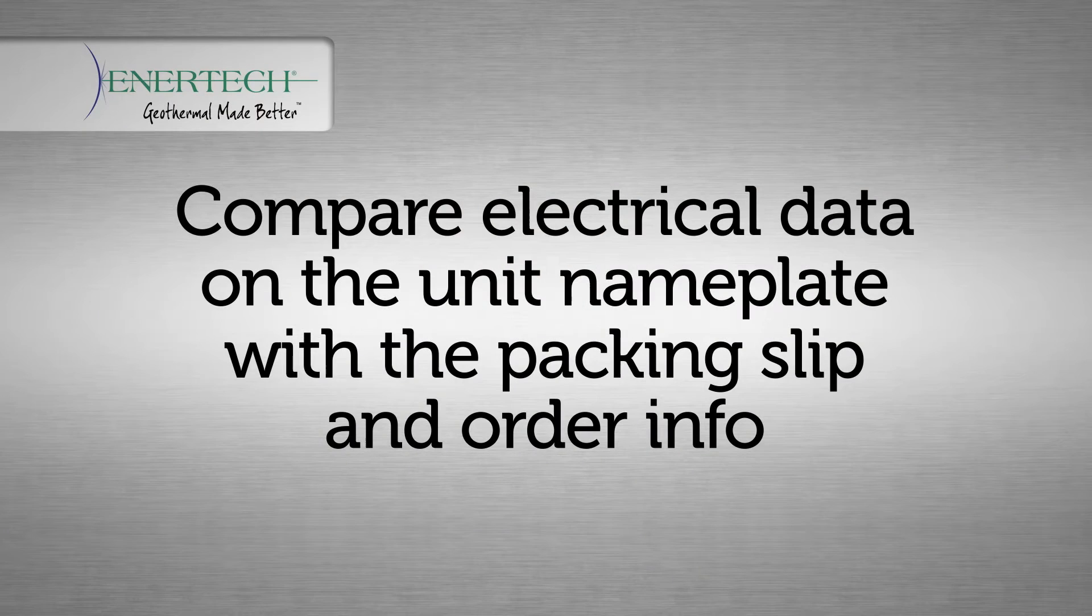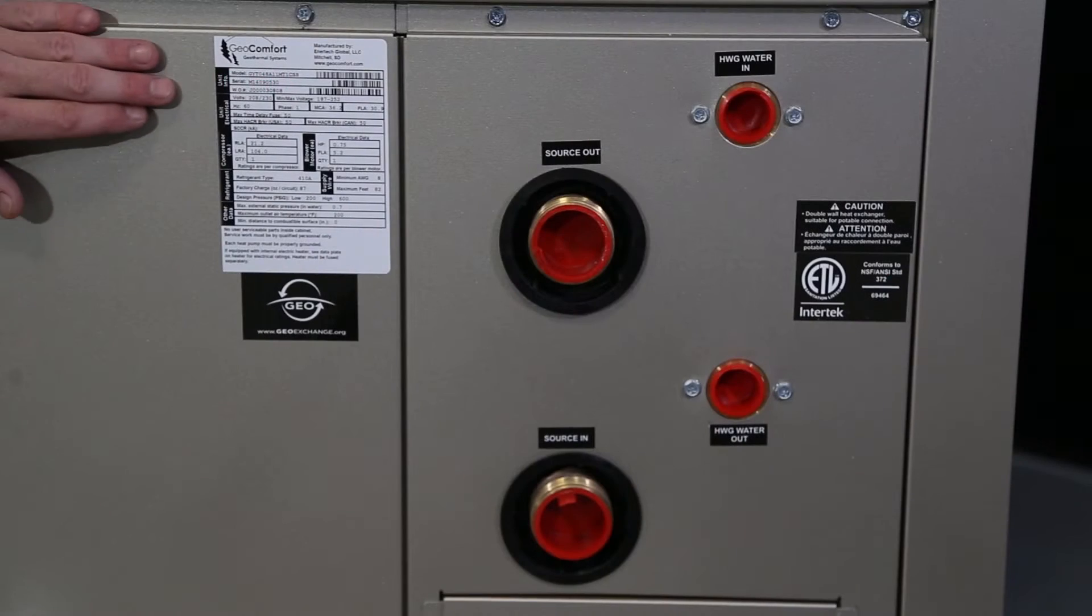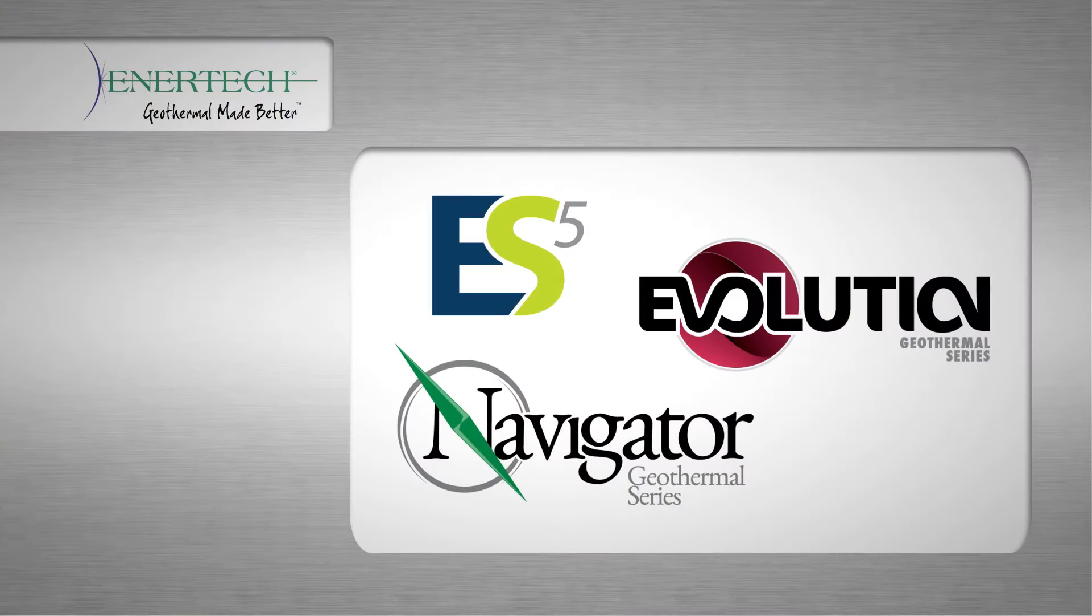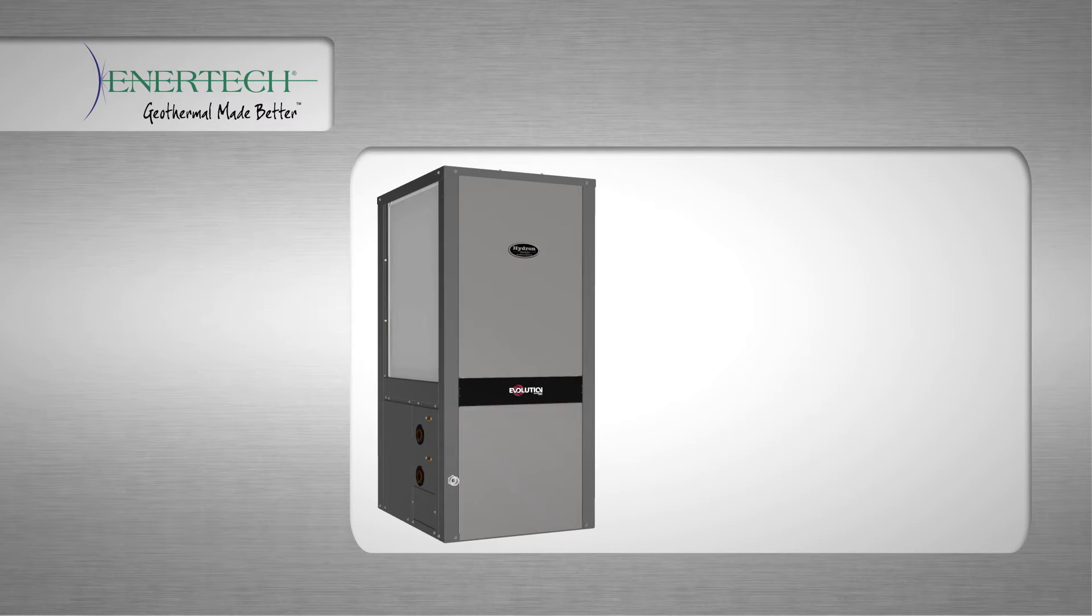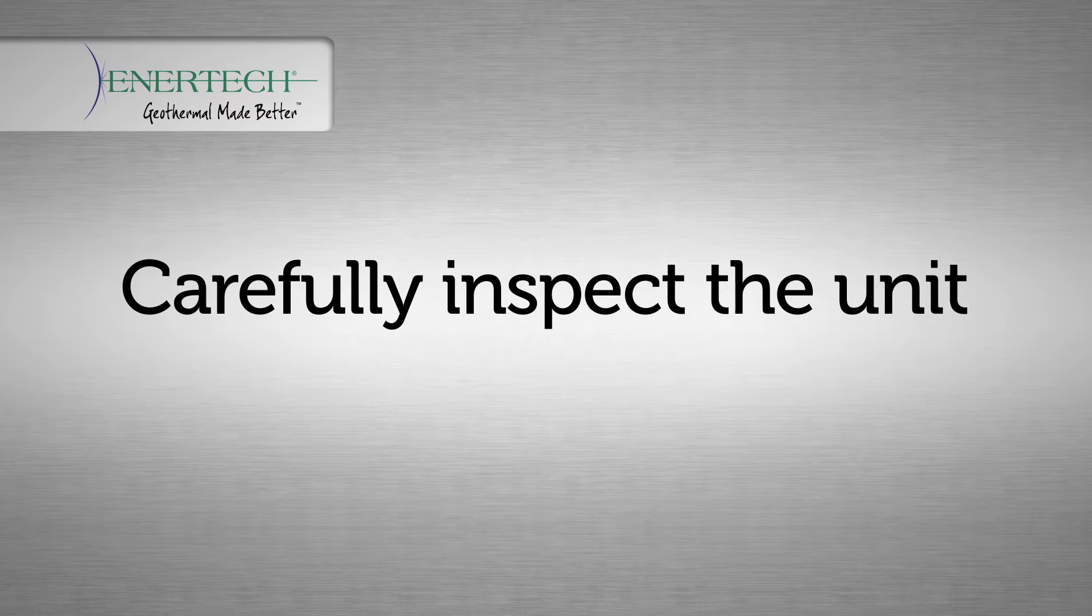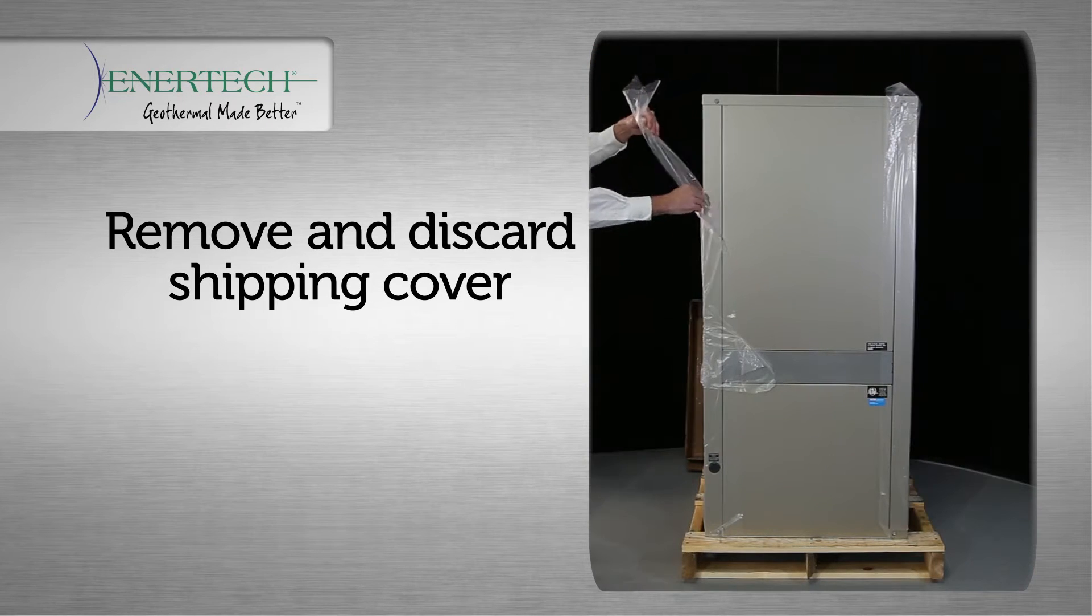Before beginning the installation, compare the electrical data on the unit nameplate with the packing slip and ordering information to verify the correct unit has been ordered and shipped. You'll want to carefully inspect the unit before beginning installation. Remove and discard the air coil protective shipping cover.